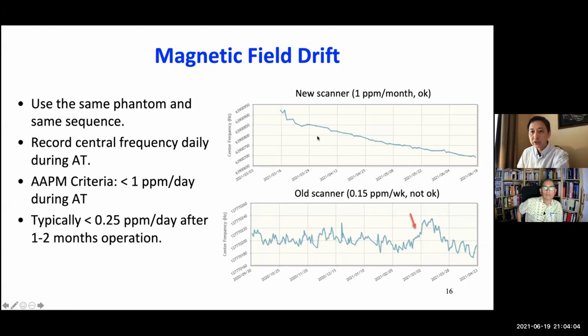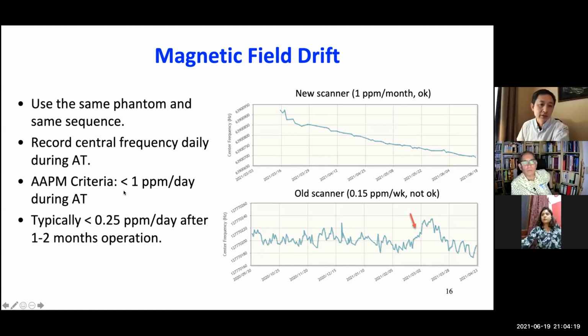This looks terrible, but if you look at the number, it's actually 1 ppm per month. So this is perfectly fine. We don't need to worry about it. Okay, 1 ppm for 1.5T is 64 hertz per month, and well within the criteria of 1 ppm per day recommended by the AAPM. AAPM also recommends a typical 0.25 ppm per day after 1 to 2 months of operation, okay? This is just a recommendation.